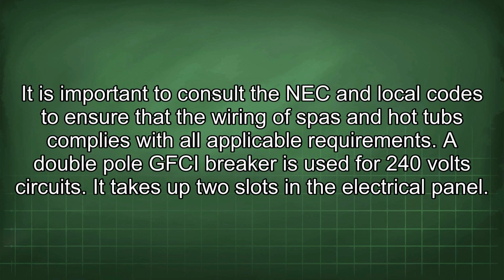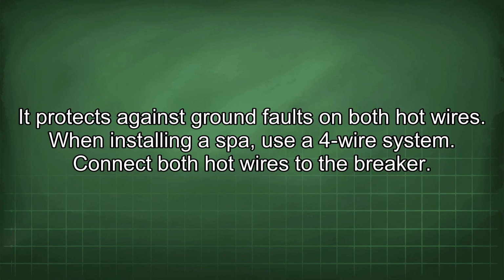It is important to consult the NEC and local codes to ensure that the wiring of spas and hot tubs complies with all applicable requirements. A double-pole GFCI breaker is used for 240-volt circuits. It takes up 2 slots in the electrical panel. It protects against ground faults on both hot wires.